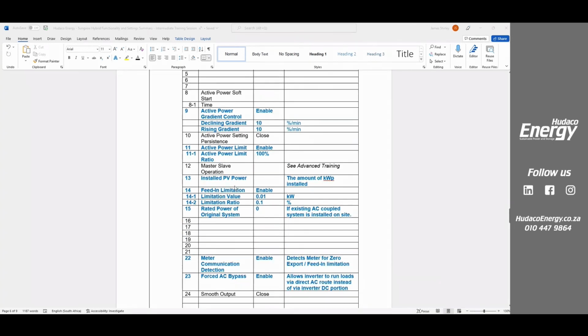Okay. Your installed PV power. This is the kilowatt peak that you've got installed on the site. So this will be different for every client. You might have some clients with 4 kilowatts, some clients with 12 kilowatt peak on the same or a similar system. Feed-in limitation, this is what we do for that zero export. Please, if you disable this, you're just going to feed back all the time. If you've got a prepaid meter from Conlog, it's going to go into tamper mode. You can get an LLR to remove that, but please just be aware that the prepaid meters absolutely don't like it. Eskom's normal meters also don't like it too much.